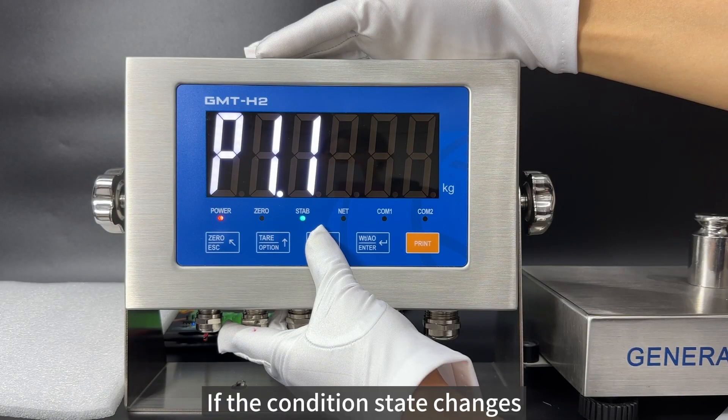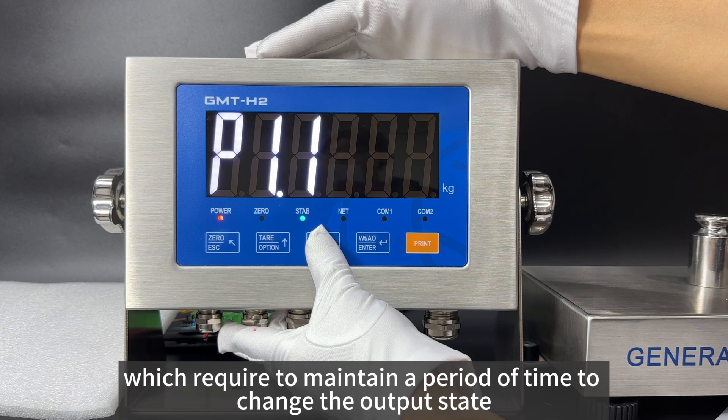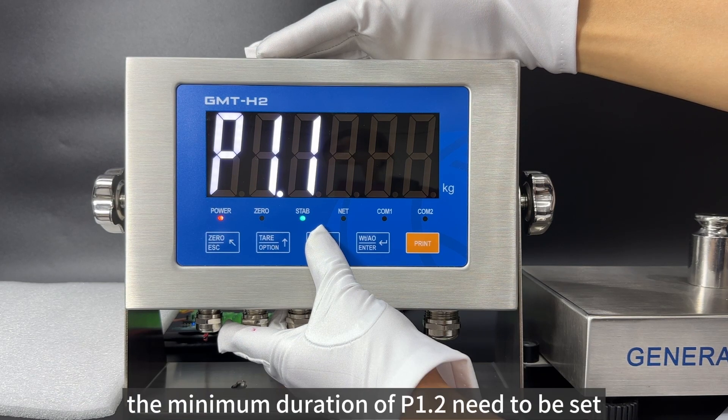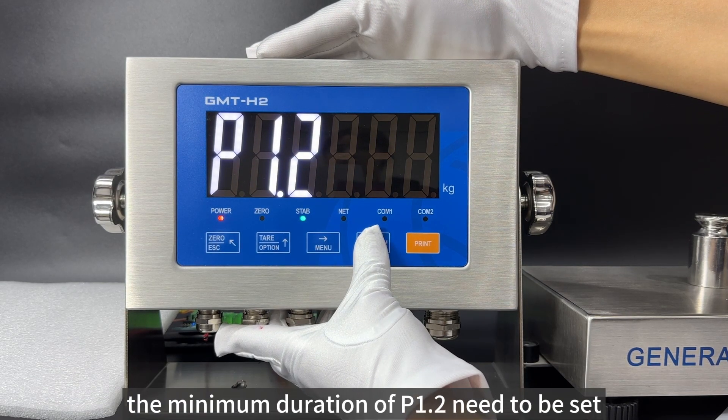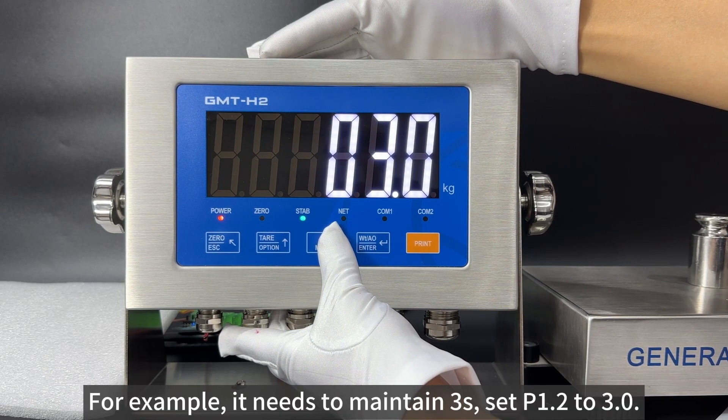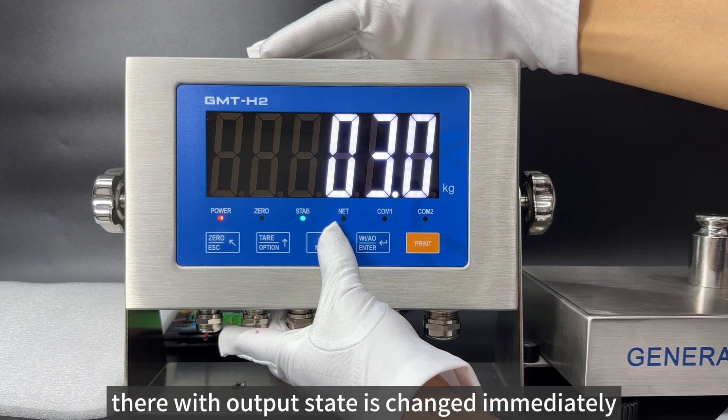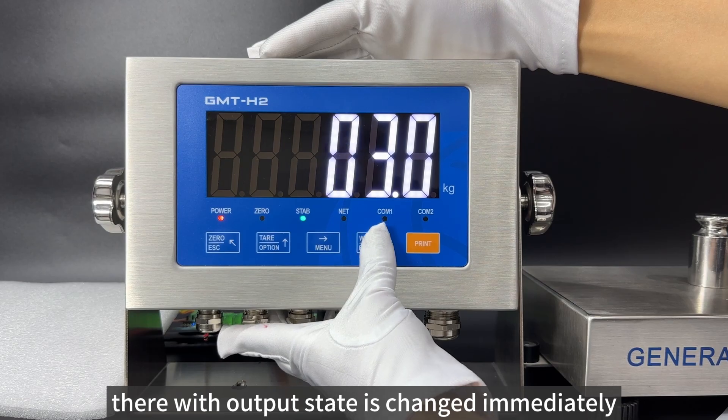If the condition state change requires maintaining a period of time to change the output state, the minimum duration of P1.2 needs to be set. For example, if it needs to maintain 3 seconds, set P1.2 to 3. Set to 0 means when the condition state changes, the output state is changed immediately.